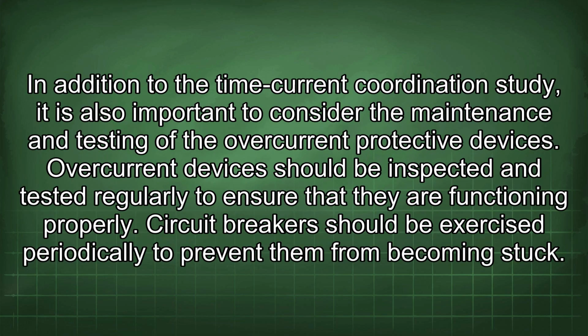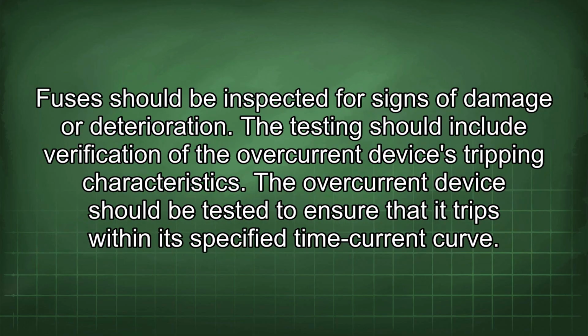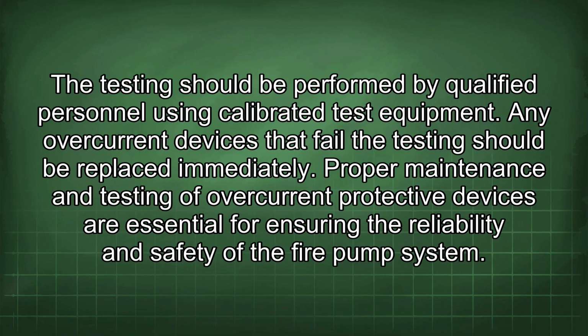In addition to the time current coordination study, it is also important to consider the maintenance and testing of the overcurrent protective devices. Overcurrent devices should be inspected and tested regularly to ensure that they are functioning properly. Circuit breakers should be exercised periodically to prevent them from becoming stuck. Fuses should be inspected for signs of damage or deterioration. The testing should include verification of the overcurrent device's tripping characteristics. The overcurrent device should be tested to ensure that it trips within its specified time current curve. The testing should be performed by qualified personnel using calibrated test equipment. Any overcurrent devices that fail the testing should be replaced immediately.